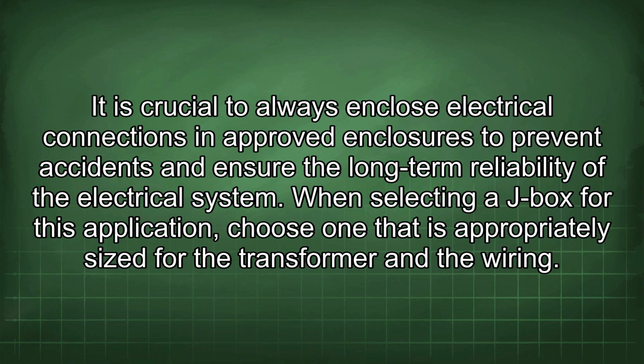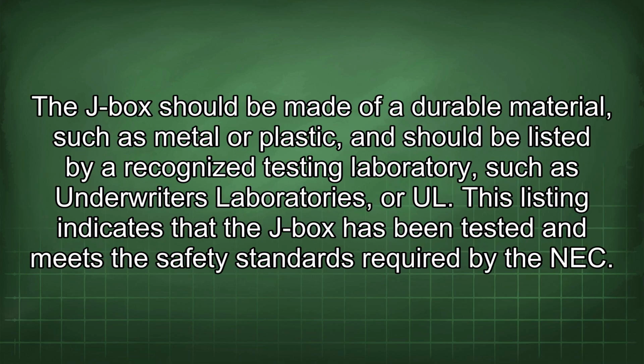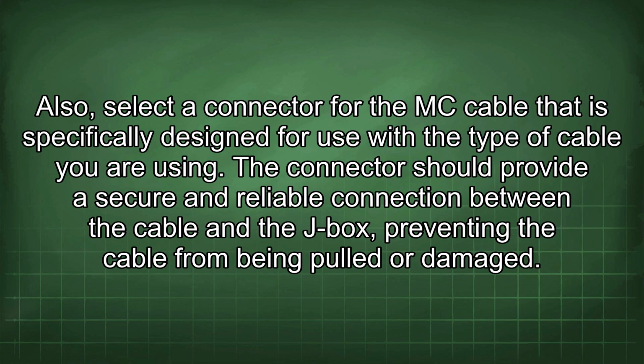When selecting a J-box for this application, choose one that is appropriately sized for the transformer and the wiring. The J-box should be made of a durable material such as metal or plastic, and should be listed by a recognized testing laboratory such as Underwriters Laboratories or UL. This listing indicates that the J-box has been tested and meets the safety standards required by the NEC. Also, select a connector for the MC cable that is specifically designed for use with the type of cable you are using. The connector should provide a secure and reliable connection between the cable and the J-box, preventing the cable from being pulled or damaged.